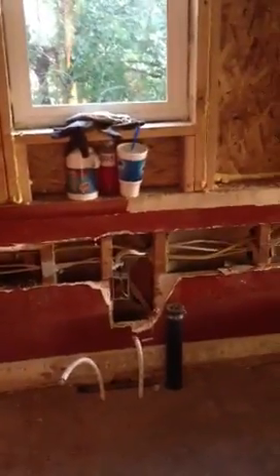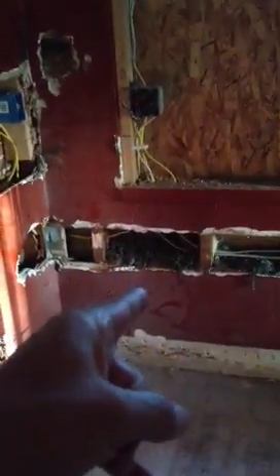We have a fridge, we have our stove — there's a 110 outlet here — and overhead lighting. Fridge, stove, and overhead are all good. What you do not have is a dishwasher circuit. You need a dishwasher circuit for sure. The disposal is there but you should have a dishwasher right there according to the plan. So we need a dishwasher circuit. Overhead is okay.